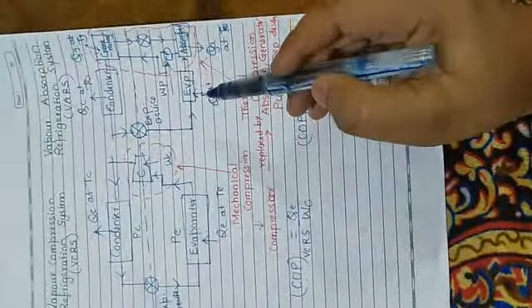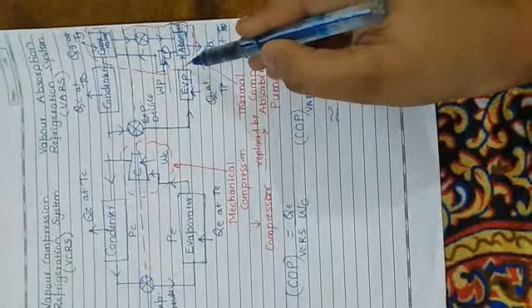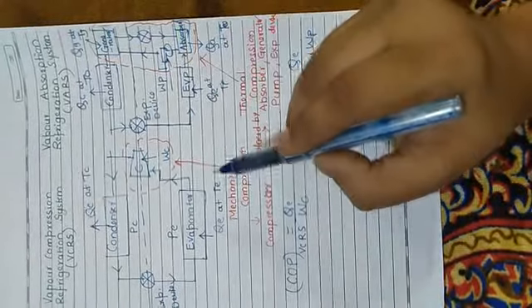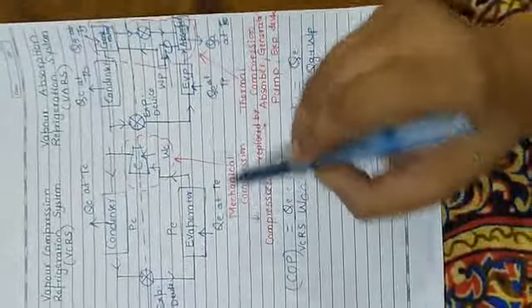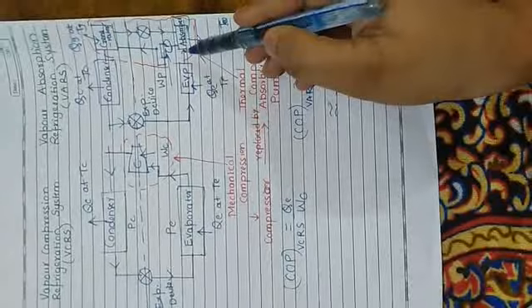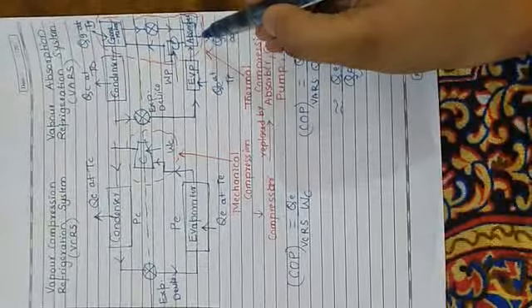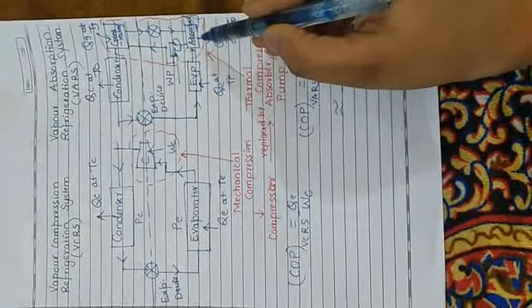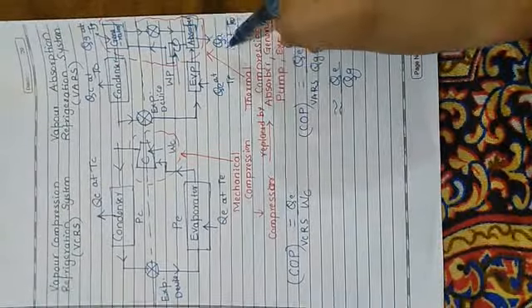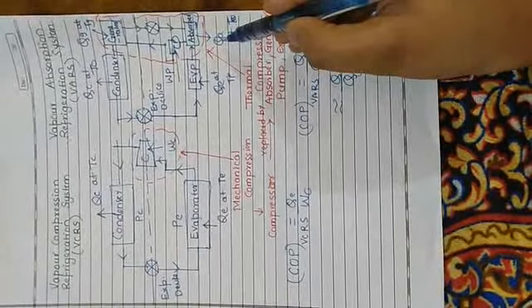Now we will quickly see its working. The low temperature, low pressure refrigerant absorbs heat in the evaporator. The refrigerant vapors are absorbed by the weak solution in the absorber. Here weak means weak in refrigerant. This reaction in absorber is exothermic. So heat is rejected by the absorber. We denote it by QA.